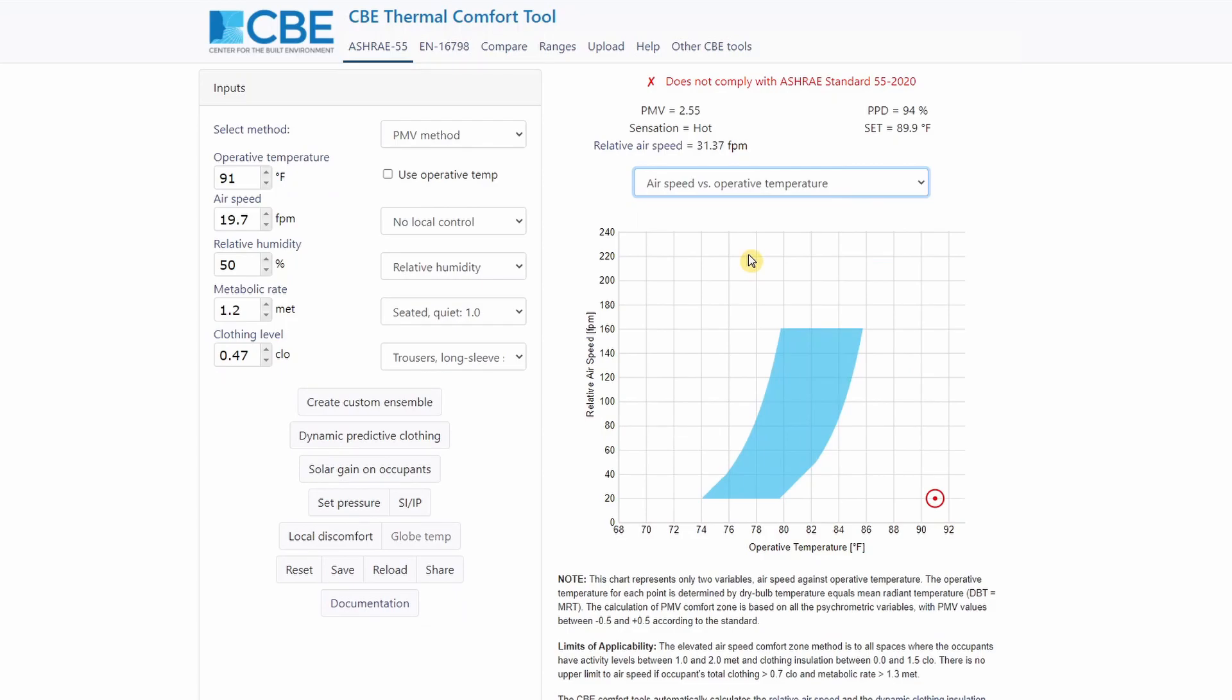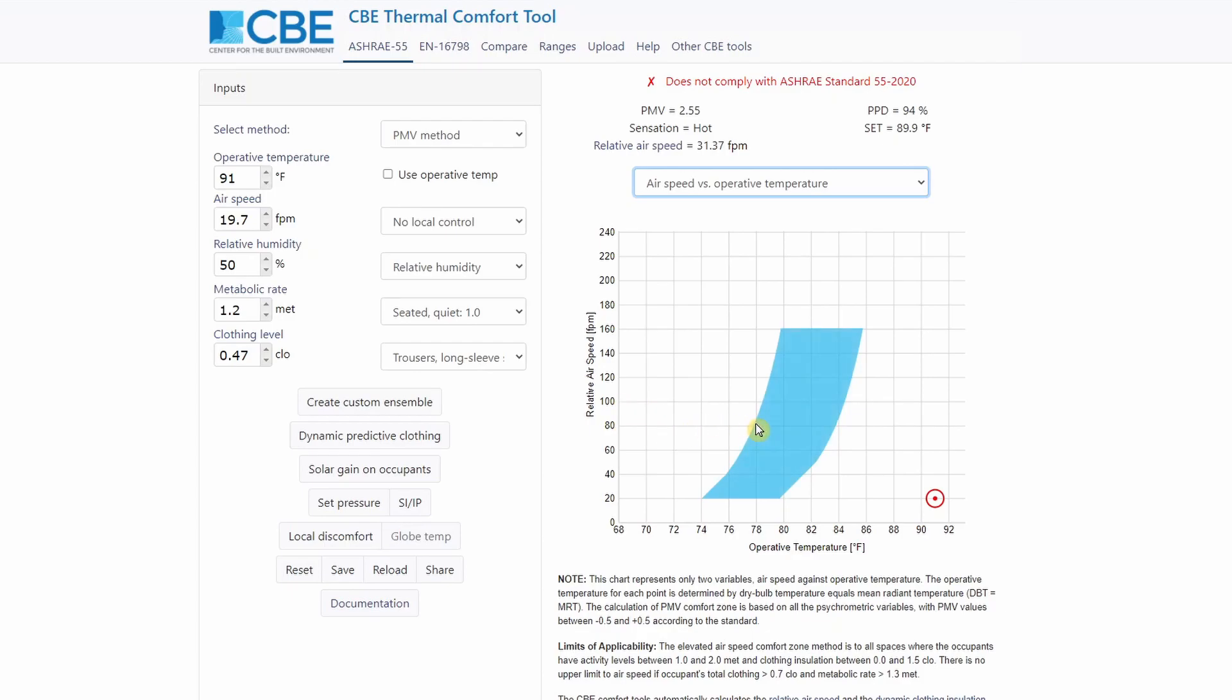You can select the airspeed versus operative temperature. This chart is quite useful if you want to understand the impact of increasing airspeed on the thermal comfort region. You can see that for this specific airspeed 20 feet per minute, people will be comfortable with a temperature ranging between roughly 74 and 80 Fahrenheit. If you have an airspeed of 80 feet per minute, then people will be comfortable between 78 Fahrenheit and 84 Fahrenheit.